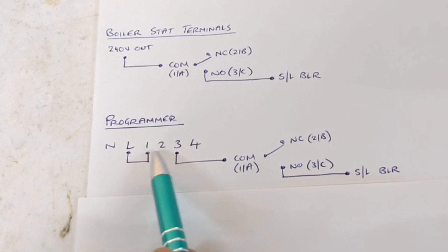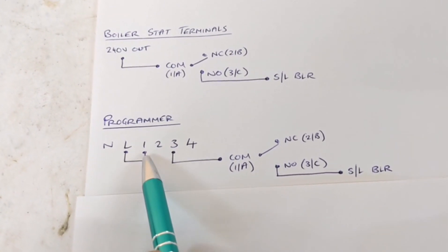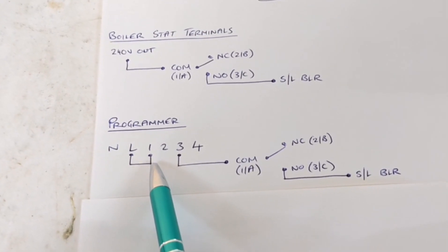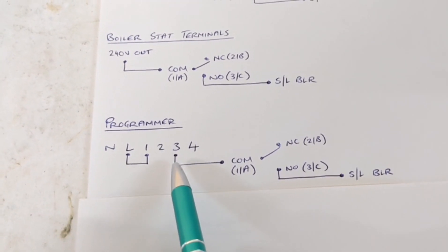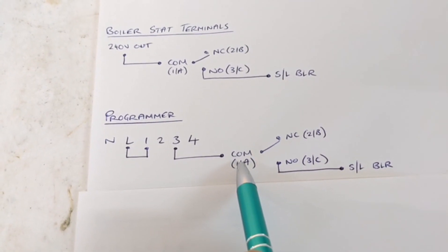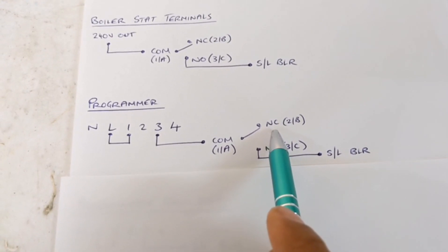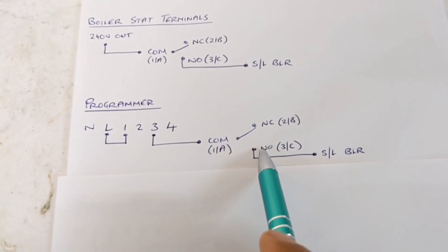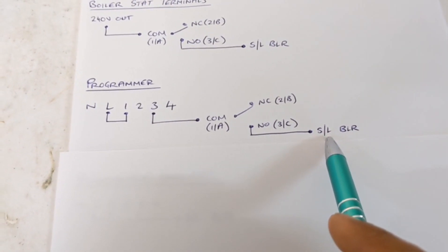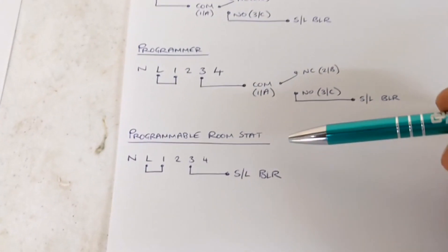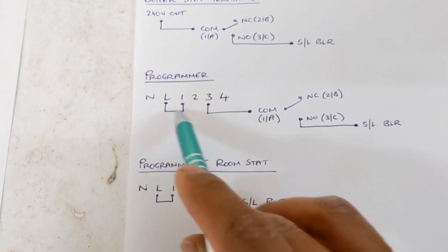At rest, the 240 volts is sitting between terminals one and two, not doing anything. When you turn the programmer on, that sends 240 volts to number three, which is the common on the programmer. That then starts the sequence: 240 volts to the common on the room stat, to normally closed, then when you turn the heat up it goes to normally open and then goes to the boiler and gets it to fire up.